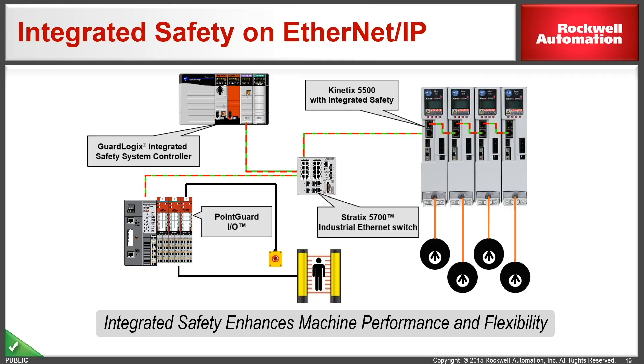So from an architecture standpoint, the elimination of the contactors, the safety relays, and all the hardwiring that's associated with it definitely cleans up our architecture. It makes our layout much cleaner and much more flexible. So you're using safety I/O, whether that be some type of point guard I/O or armor point safety I/O. You're wiring safety devices into safety I/O, they are monitored over the ethernet network, and then commands are sent down to the drive over that same ethernet network.